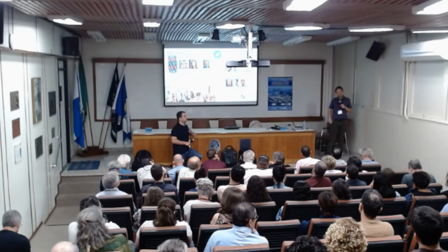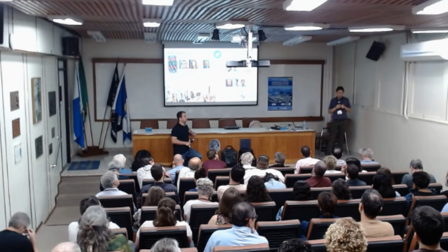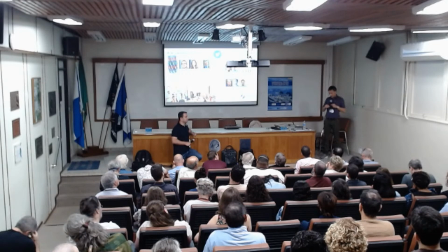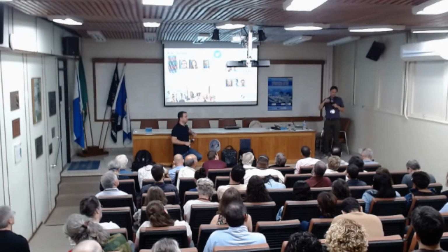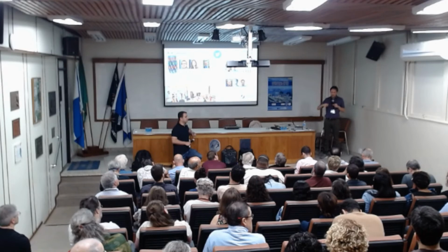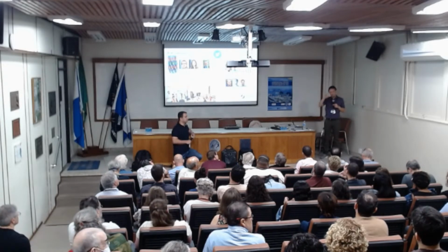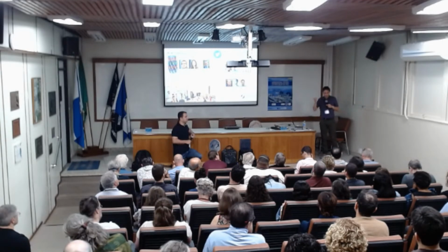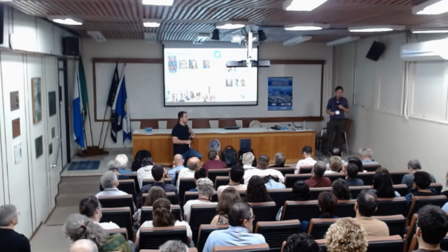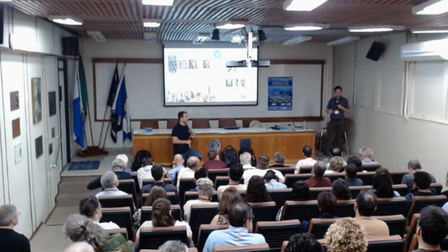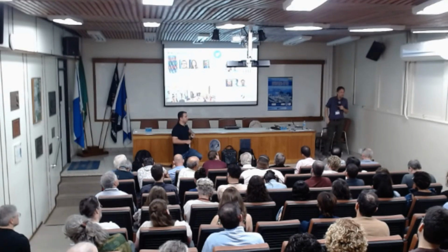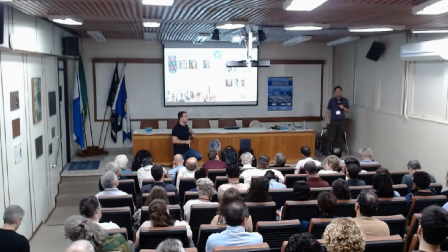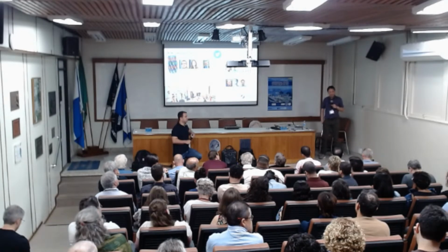So this is something where these new hybrid detectors will play a role, and there is already Timepix development, so you basically don't read out frames, but you do event detection, and you can then virtually make frames, and this will be extremely fast. So I think there's hope that we can come down to seconds of exposures, on a similar scale to what we are used to. But we are not there yet. That's totally right, and automation isn't there. It's all sitting at the microscope, pushing buttons like in the old days.